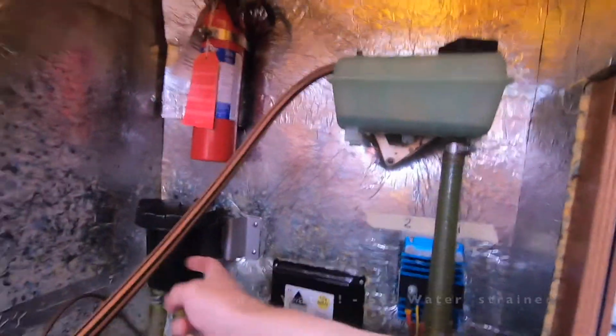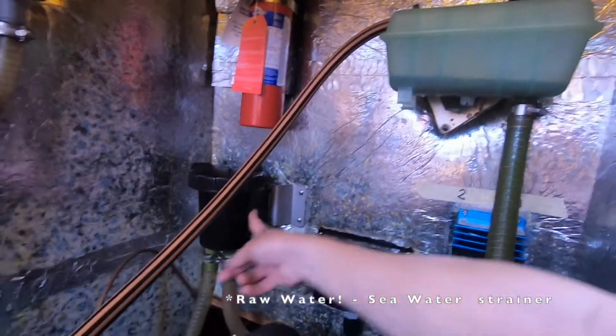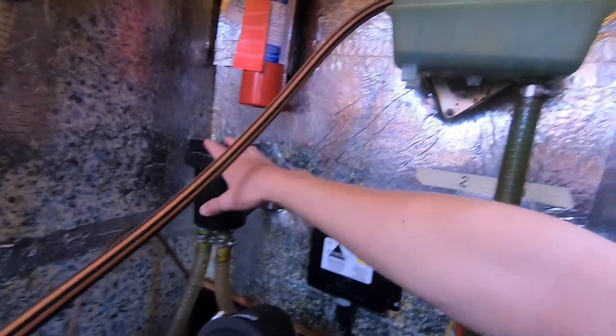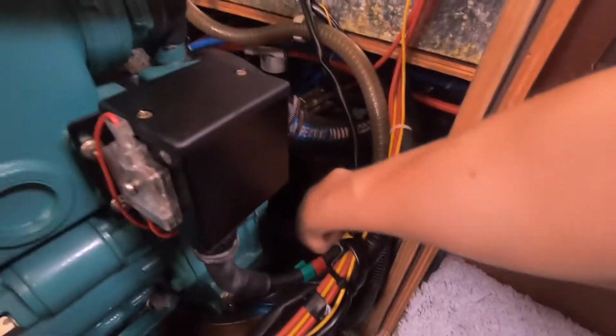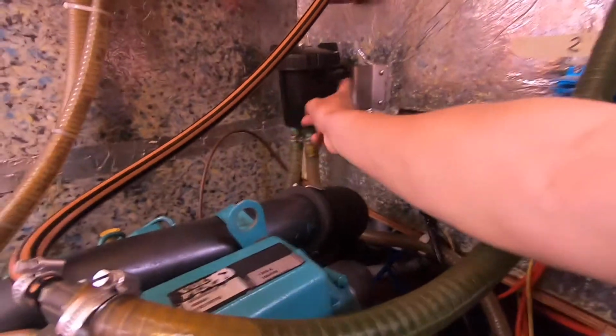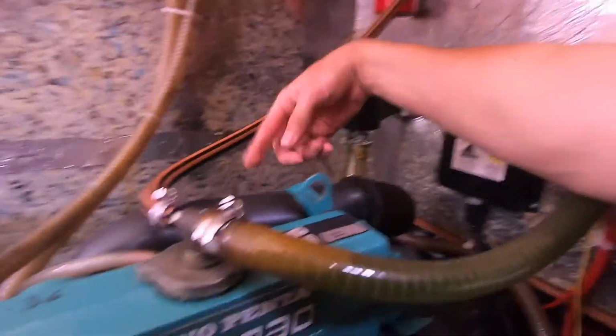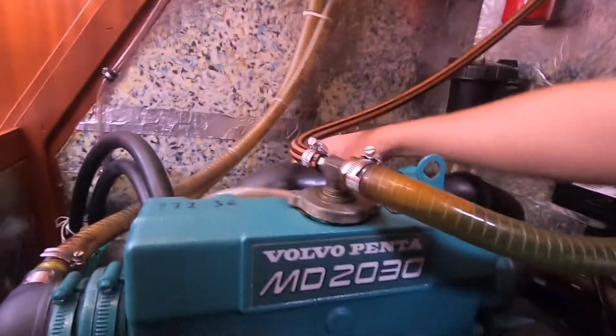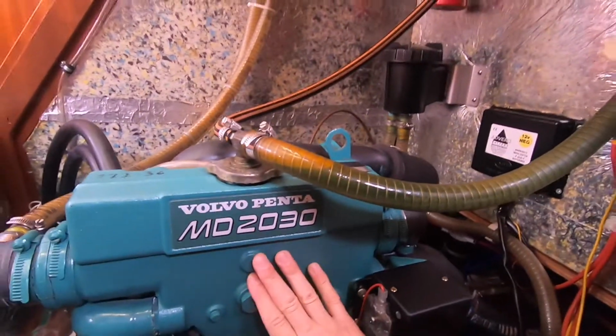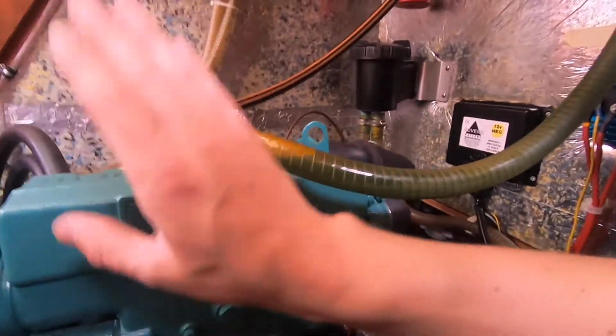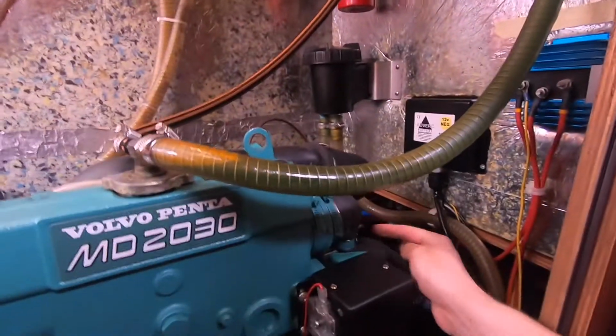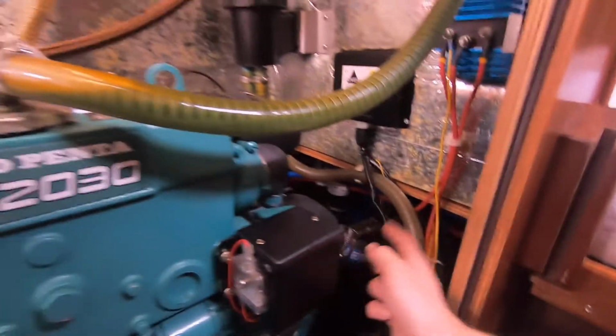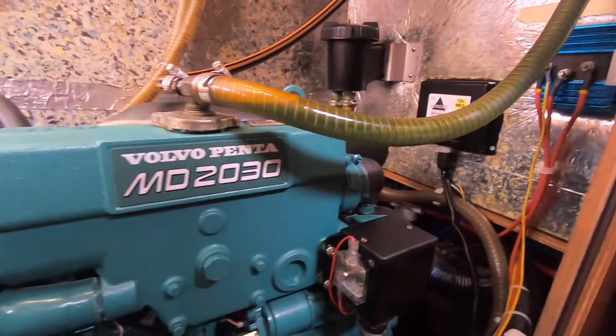Header tank, fresh water strainer is in there, so when the water comes into this engine at the front through the seawater pump, before it comes in it goes up the pipe through the leg to the seawater strainer to make sure there's no bits in it that would knacker the pump, because it's just a rubber impeller. Out through the pump, through the heat exchanger, because the engine is fresh water cooled, and then that gets dumped back down the exhaust and out it goes. That's what you see coming out the back of the yacht.